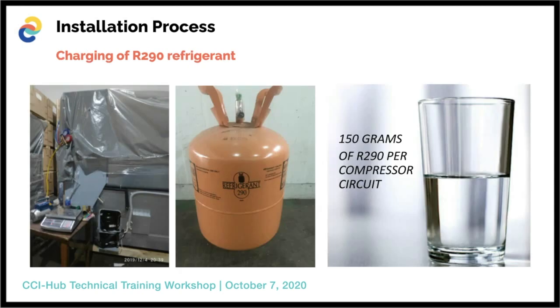charging of R290 refrigerant. As you can see in the pictures, we have three pictures: the tools, the R290 cylinder, and a glass of water as a comparison. Before charging the R290 refrigerant on the system, we use two steps. Number one is preparation of basic tools and materials needed for installation, such as oxygen-free dry nitrogen, micron gauge, pinch-off tools, shut-off valves, refrigerant hose and gauge, weighing scale, and especially combustible gas leak detectors, and most of all, vacuum pumps.